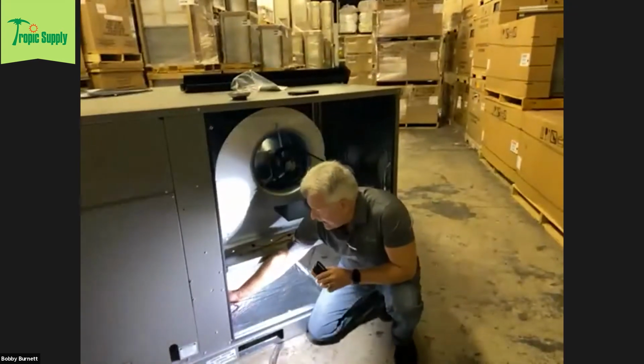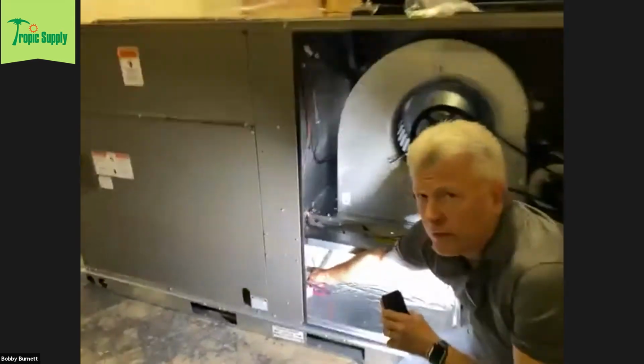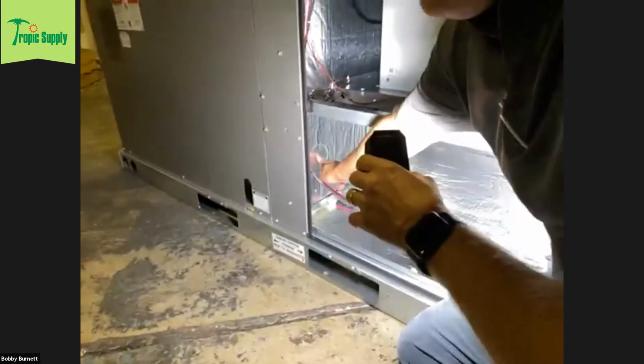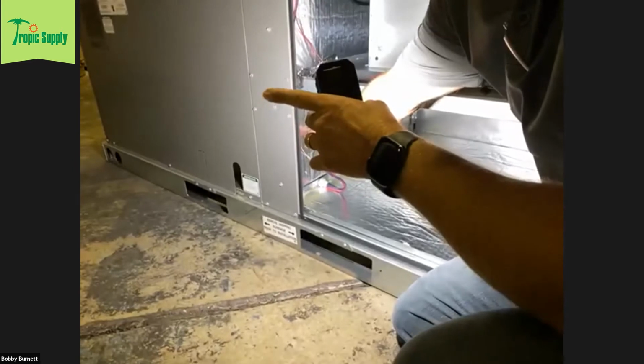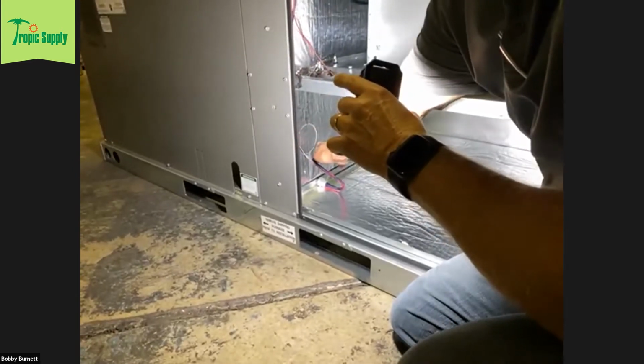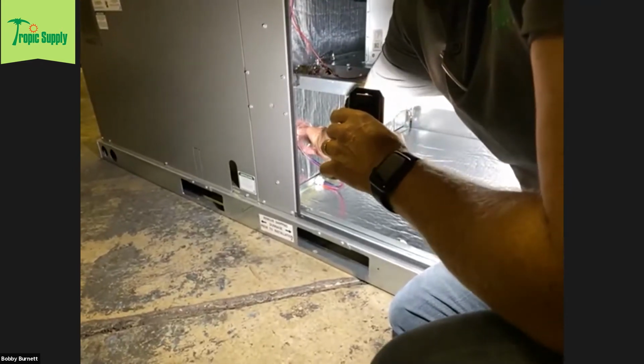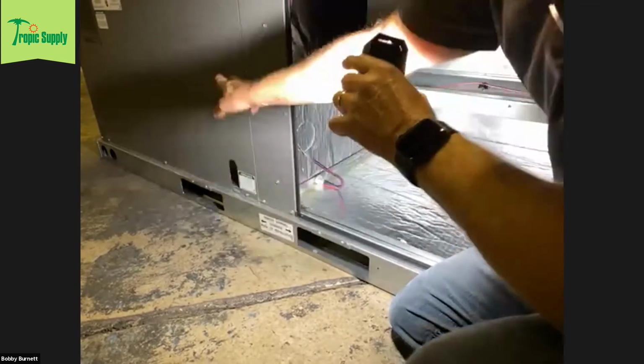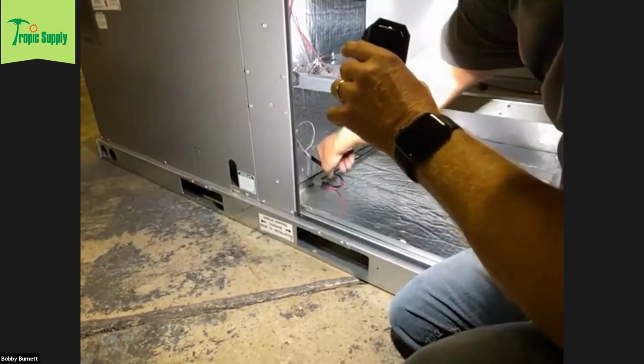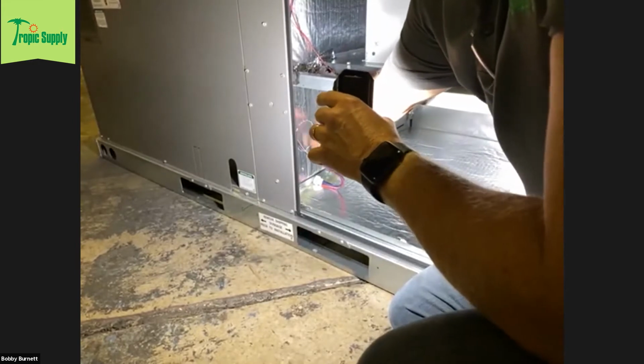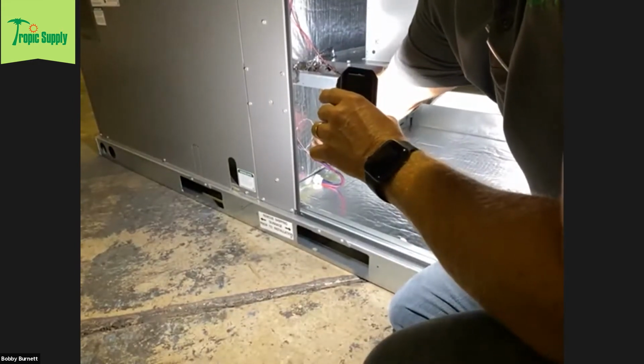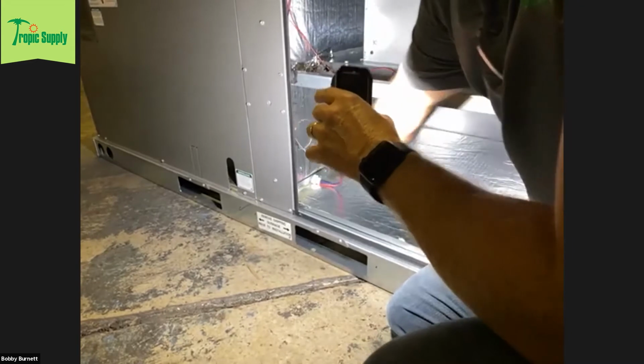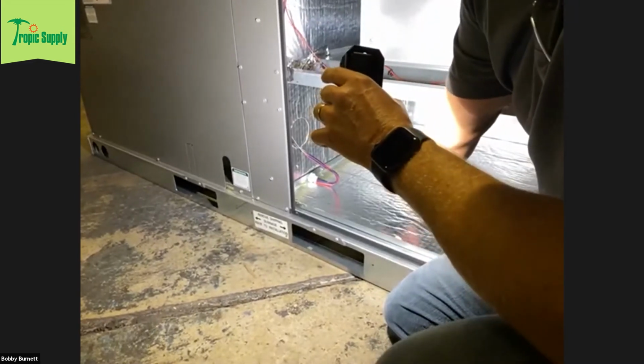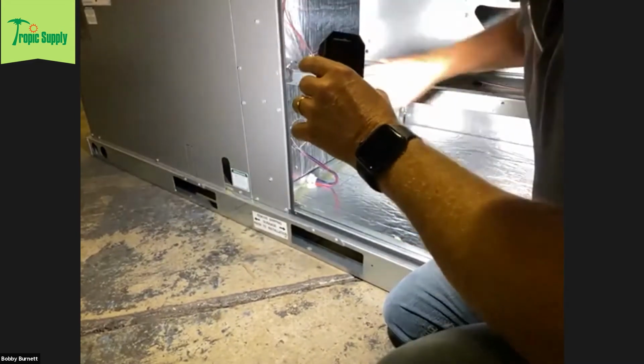Right here there's a cutout in the insulation for a knockout, and that knockout is for the single point wiring kit, which we're going to install real quick to show you how that goes in. You simply pull this insulation away to get a better view of the knockout on the other side. There's a ring that comes with the single point wiring kit so you can mount it in there and feed wires through to the heat strip, so you only need one source of power to run the unit and the heat strip.